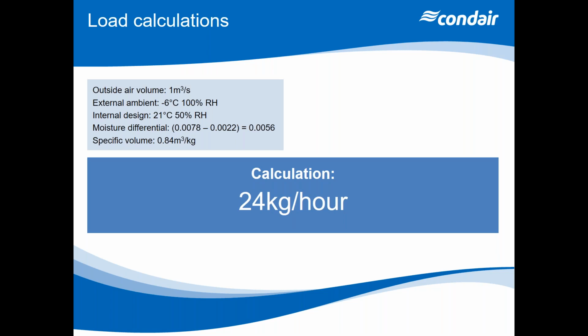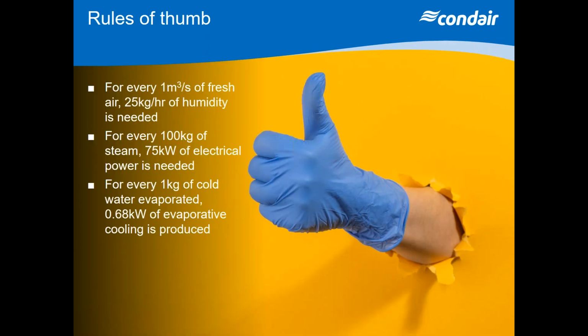Rules of thumb are pretty useful, actually. In fact, we've got 3 rules of thumb here. That's the first one: for every meter cubed per second of fresh air, it's going to give you 25 kilograms of humidity required. And for every 100 kilograms of steam you're providing electrically, it's roughly 75 kilowatts of electrical power that's required.